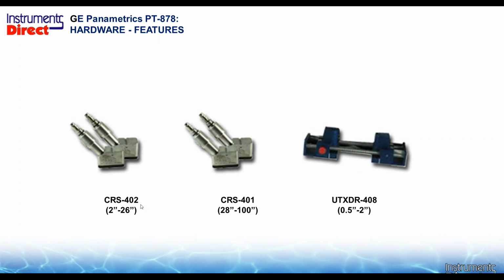So for the 402, nobody really defines the pipe sizes, but we've been doing this since 1977, so this is what we do. The 1 megahertz sensor we use from 2 to about 26 inches. You can install them on larger line sizes too. It's a function of the quality of the pipe. So generically speaking, this is what we do. When you go to larger pipe sizes, then we would consider the 0.5 megahertz transducer.